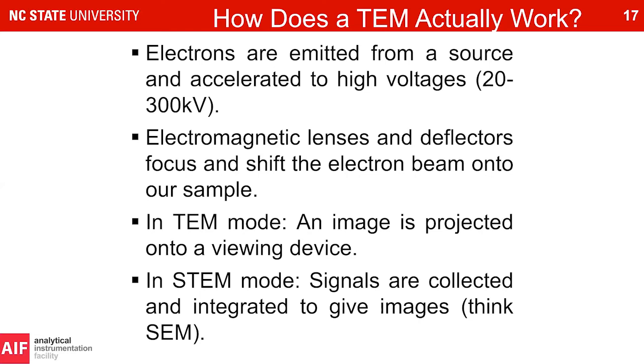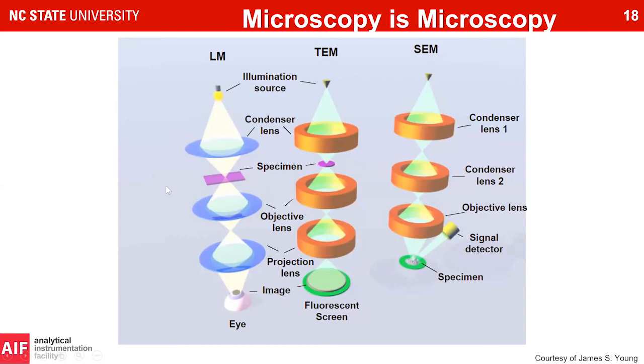If we compare an electron microscope to a light microscope, ignoring 99% of the optical components, they are actually incredibly similar: an illumination source, a condenser lens to collimate the beam and project it onto the specimen, an objective lens to form images, and a projection system to magnify and project the image onto a CCD, fluorescent screen, or other imaging device. The components and optical properties of TEM and light microscopes are quite similar. SEM and STEM are substantially different — they shine a very small probe onto the sample and detect integrated signals.